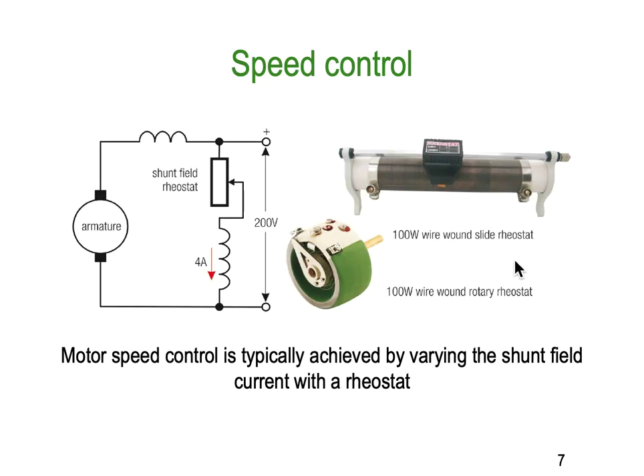Speed control: the best way to do speed control is by controlling the current through the field. We could control the current through the armature, but the armature current is normally very very high — as we saw, up in the order of 800 amps — whereas the field only takes about 4 amps. So we tend to put the speed control in the field circuit.